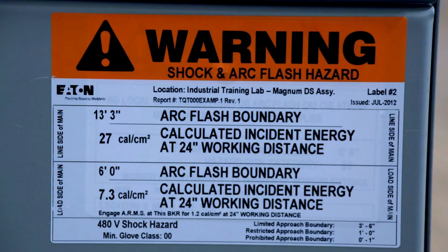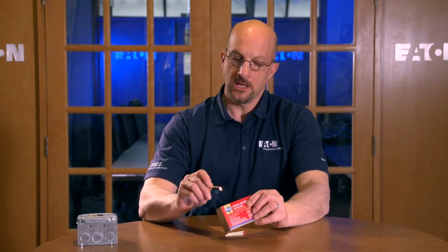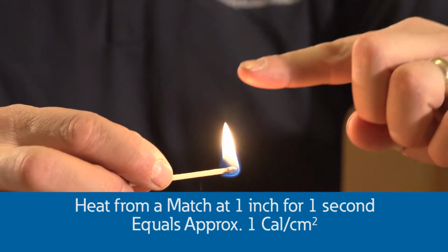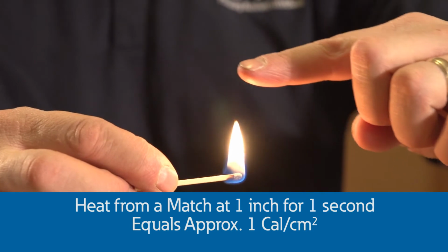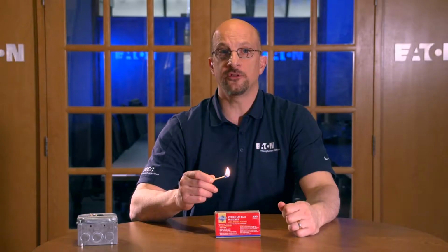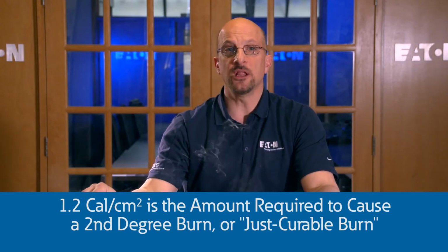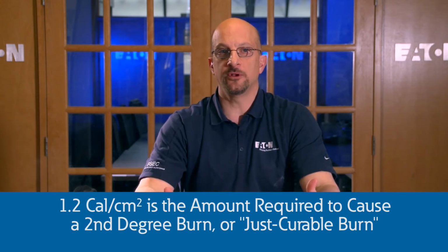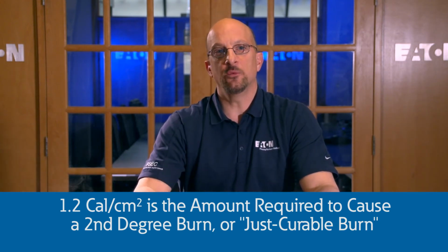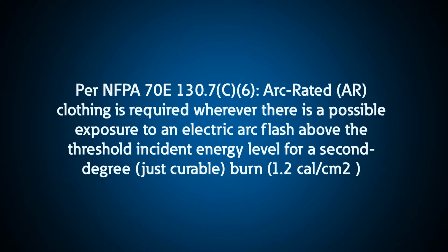An arc flash label has 2 critical pieces of information on it: the calories per centimeter squared, or the energy released, and the distance that a worker would have to stand outside to avoid a non-curable burn if an arc flash were to occur. If you held a match 1 inch under your finger for 1 second, that would be approximately 1 calorie per centimeter squared, or just below 1.2 calories per centimeter squared, the amount of heat that would be required to cause a second-degree burn, which is the limit of what we call a just curable burn.